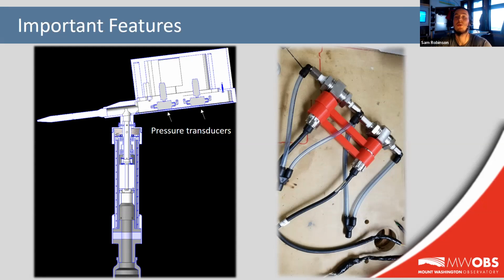Although that 0 to 10 would be suitable for most winds that we experience up here, with that range, it does begin to lose accuracy the closer it gets to that end value. And plus, we want to capture potential record-breaking wind speeds, which is where that 0 to 70 comes in handy. Having two pressure transducers also provides us redundancy in the event that one of them fails. So thanks to that larger size of Pitot 22's body and tail vane, both transducers and the pressure tubing are able to fit inside, which truly does minimize that length of the pressure lines. You can see that in that first diagram there.